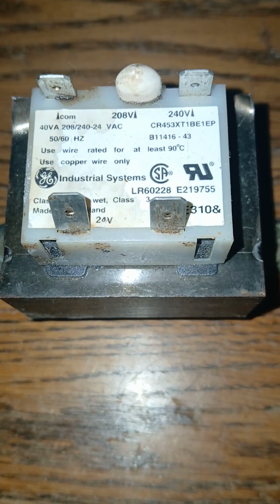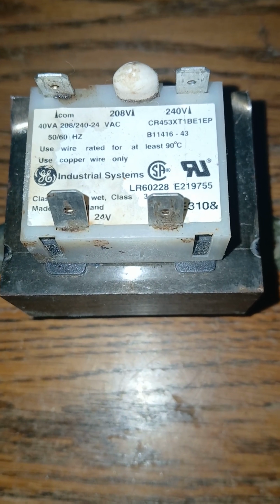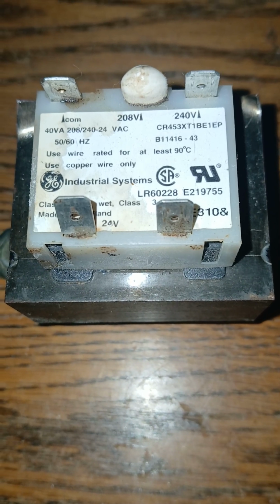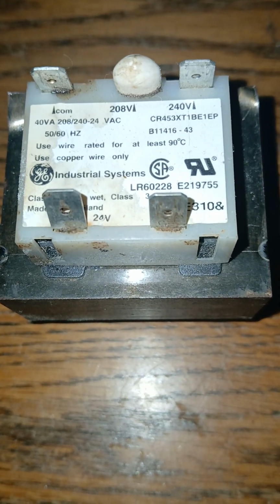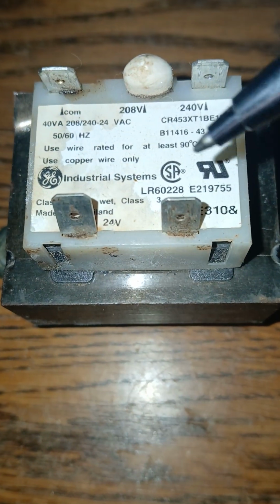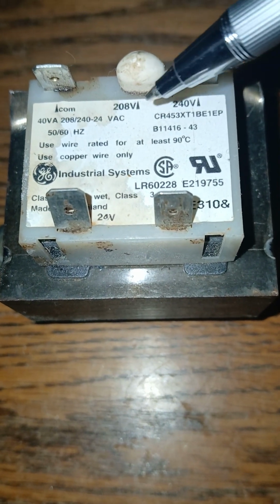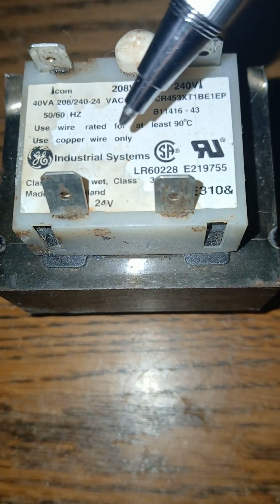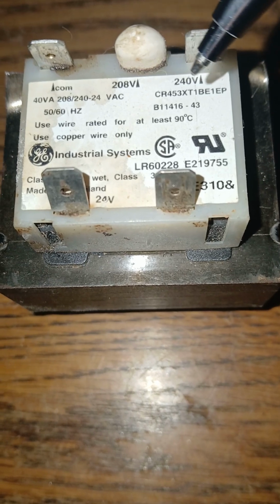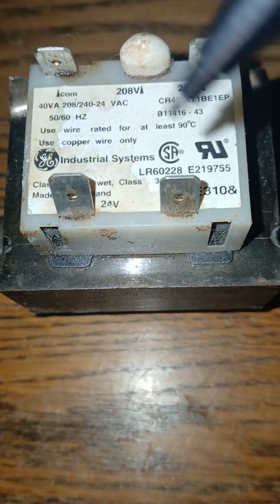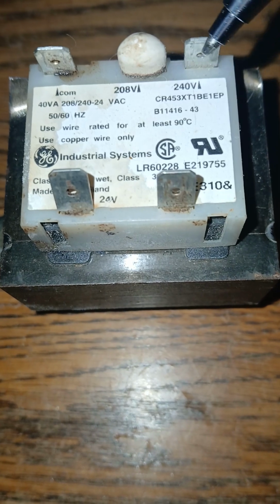But what we're dealing with is for the residential, which is normally off of the pole into the house, somewhere thereabouts 240 volts. So this transformer here can do 240 volts or 208, etc. Now it steps it down into low voltage, and in transformer, the word trans means across. So we're forming something across, going across here to here. When we step down to this side, we're at 24 volts. So we're at high voltage on this side and low voltage on this side.